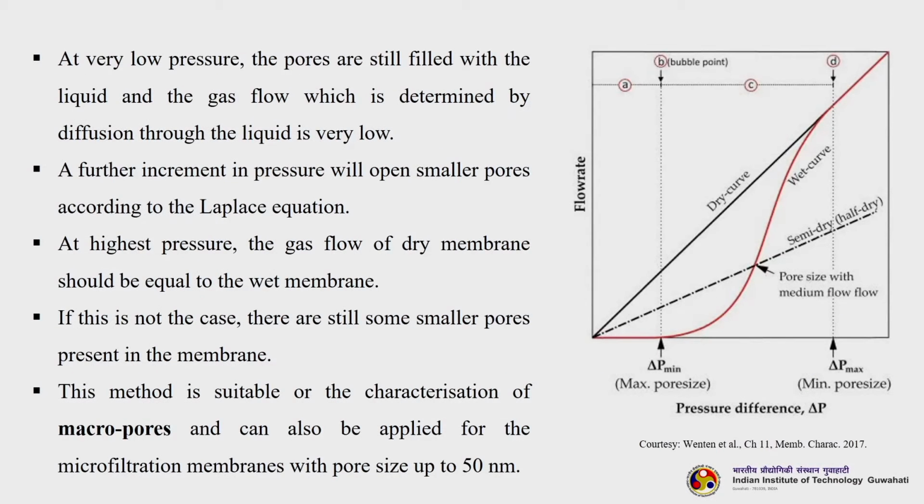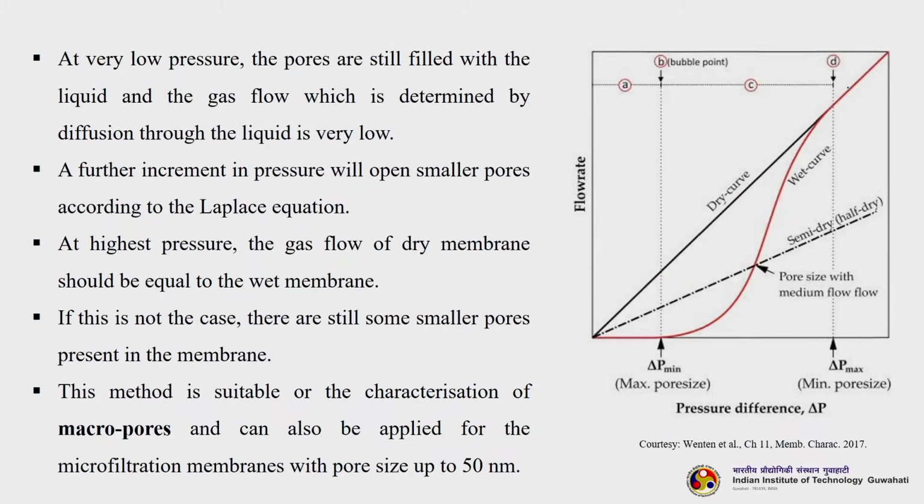At a very low pressure, the pores are still filled with liquid, and the gas flow, which is determined by the diffusion of the gas through the liquid, is very low. Now, when you increase the pressure, the smaller pores will be emptied, or they will take part in this gas flow. Okay, and at the highest pressure, the gas flow of the dry membrane should be equal to that of the wet membrane.